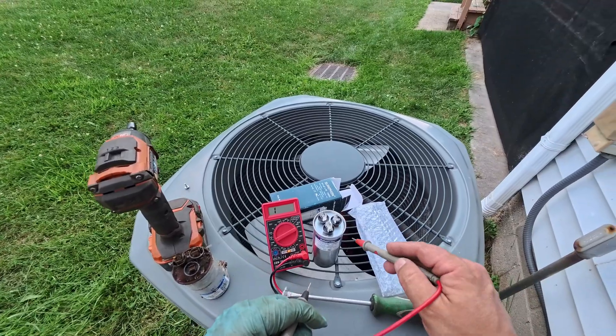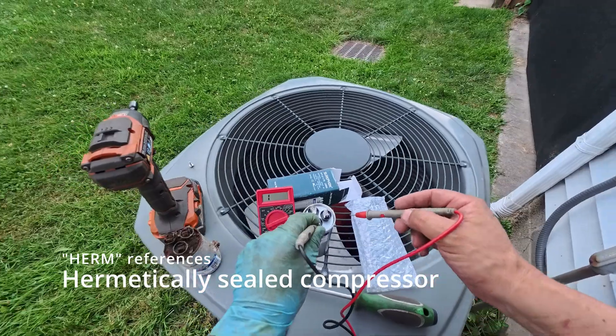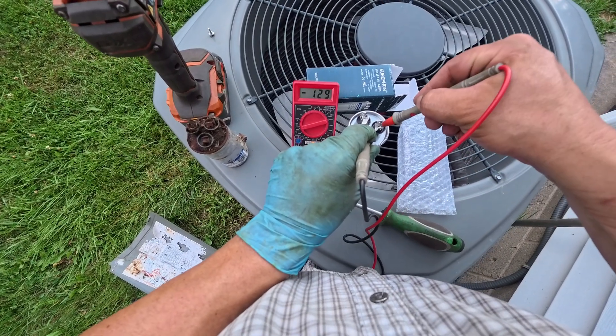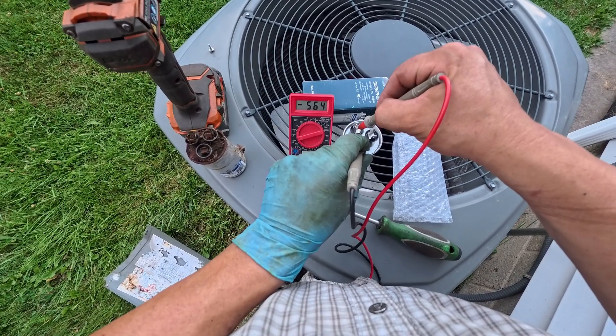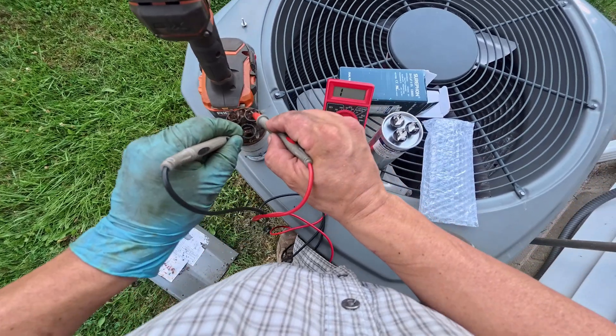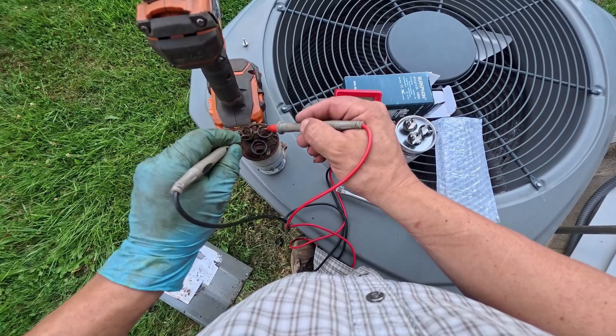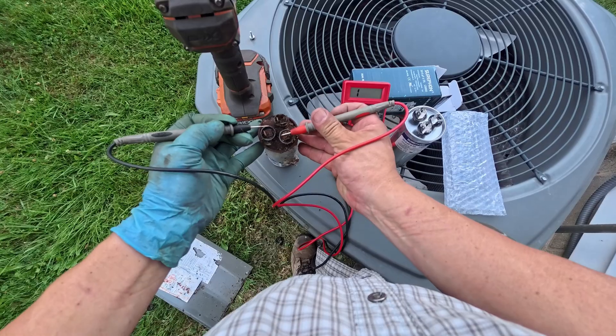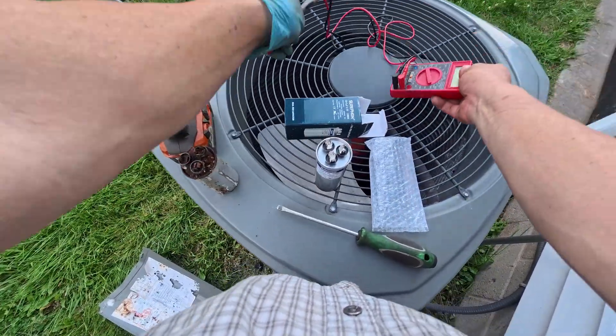These caps are usually marked on the top - got a common, fan, compressor side, and HERM (I don't know why it's called HERM, never looked it up). So you go from the common to one side - see the numbers changing - common to the other side - see the numbers changing. This one? Dead. Dead. Dead dead - got nothing. I was thinking the compressor side was actually working because that was still running, but yeah, I got nothing. Toast - it's toast. Let's get this in. It's hot inside, it's hot outside, it's hot every side.